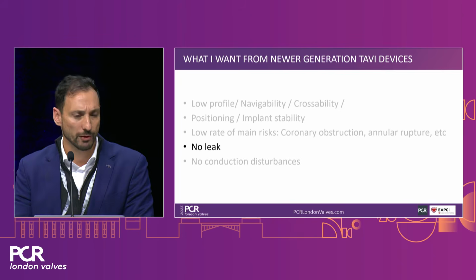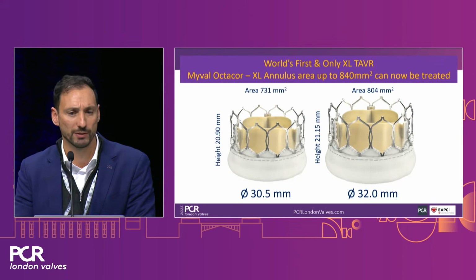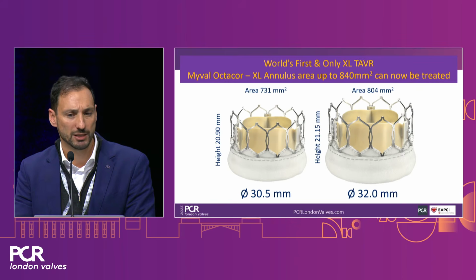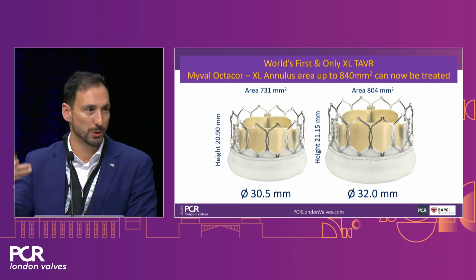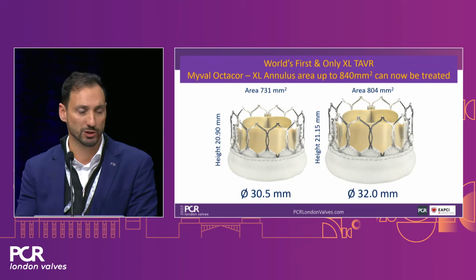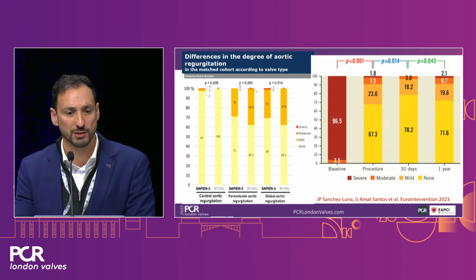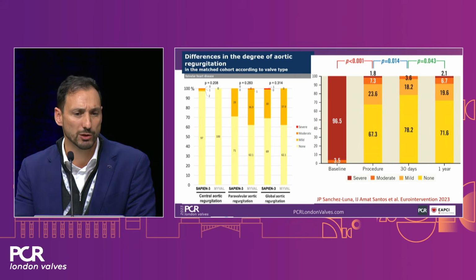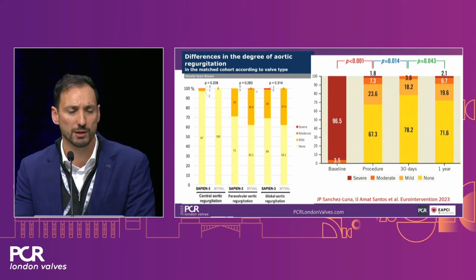And regarding the follow-up, for us it's important to achieve the best results in terms of leakage. So when we are in large anatomies, the availability of these extra large sizes with this skirt can be particularly useful to avoid leakage, which is more common when we need the SAPIEN 3 29, but we are a little bit undersized because the annulus is too big. So we are covering this range of patients, and in the MATCHBALL study, where we compared these balloon expandable technologies, we could see that the results in severe leak was virtually the same with both devices, only one case in the SAPIEN 3 arm, 0 cases of severe or moderate regurgitation in the Myval after matching for anatomical variables of the annulus.